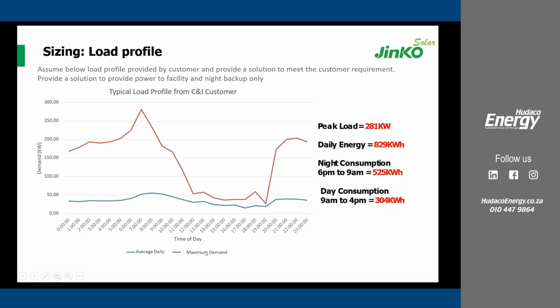But what you can also see in a typical scenario is that if we don't know the peak load, it can lead to making a wrong judgment. If we do our design based on the average load, then we size based on a system where the peak appears to be around 52 or 53 kilowatts, and we choose a 100 kilowatt system. But in real sense, the maximum demand goes beyond 250 kilowatts. Ideally, from this peak, we are looking at around 281 kilowatts.